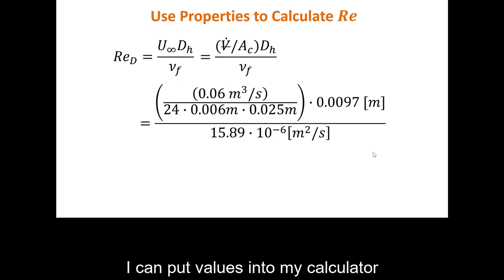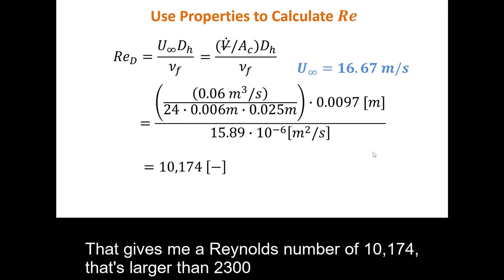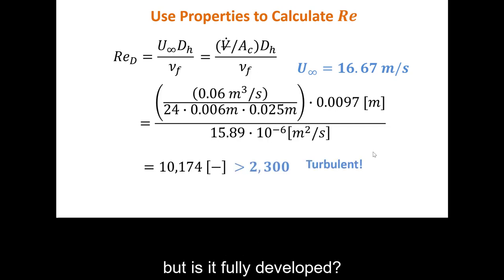I can put values into my calculator and find that the velocity of the flow in the heat sinks is 16.67 meters per second. That gives me a Reynolds number of 10,174. That's larger than 2,300, so my flow is turbulent.